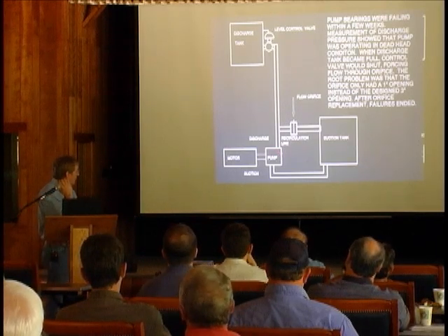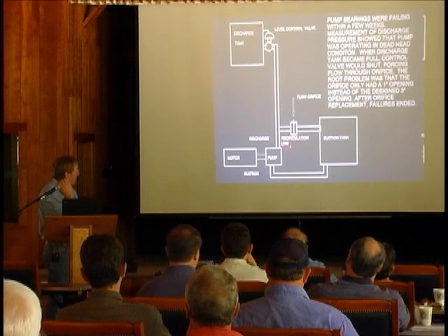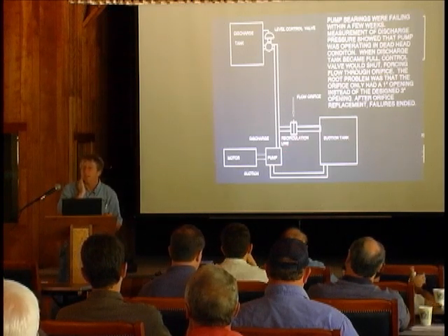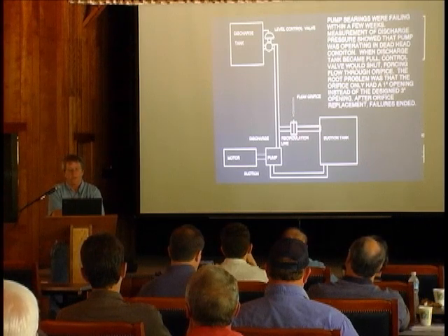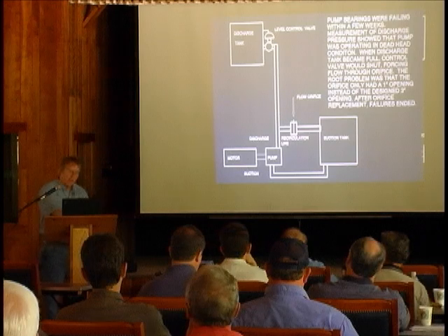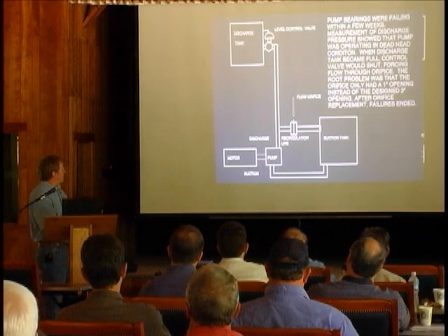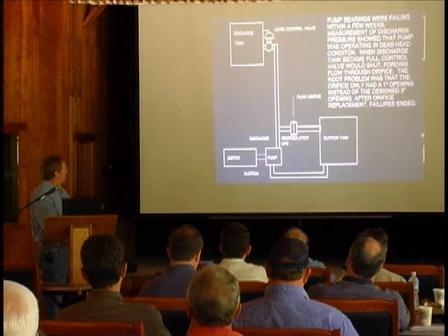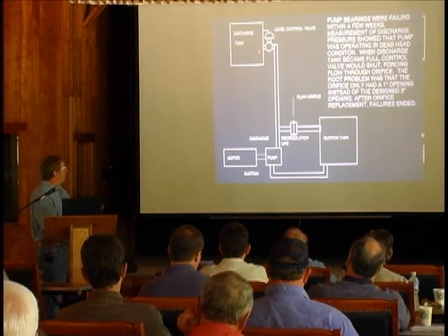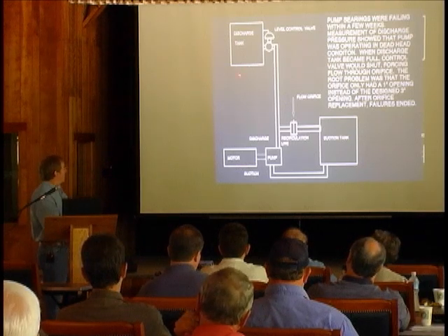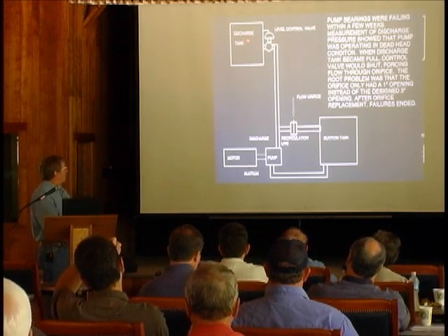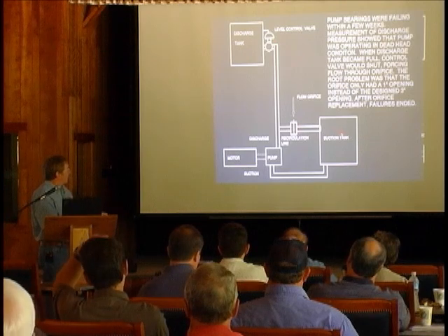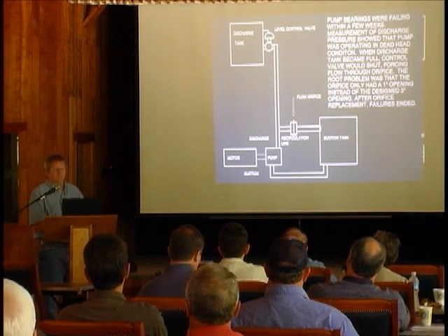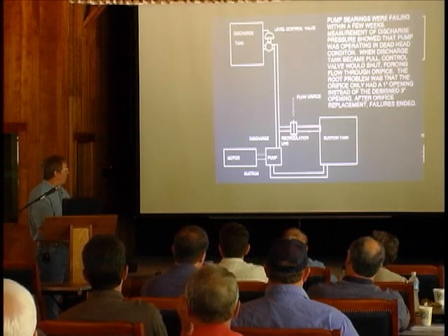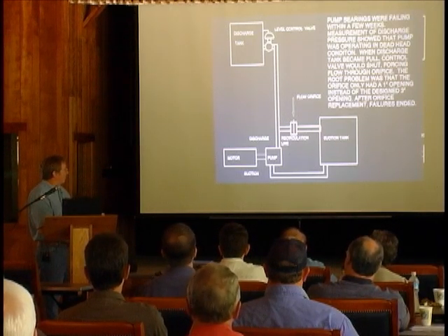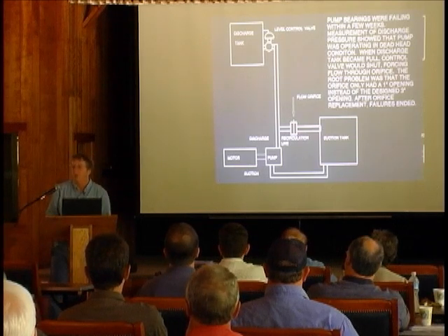So I took a gauge reading on the pump, and the gauge reading basically said it was in a deadhead condition. So I got a drawing of the system, and this pump was pumping like 7 stories up to a discharge tank. The discharge tank has a control valve, and when the level gets so high, the valve shuts off, and the pump then goes through the recirc line back to a suction tank. Very basic situation. It had a flow orifice, so you can't just flow back to the tank through a straight pipe, or you don't have enough head, and then you'll be running out on the pump.